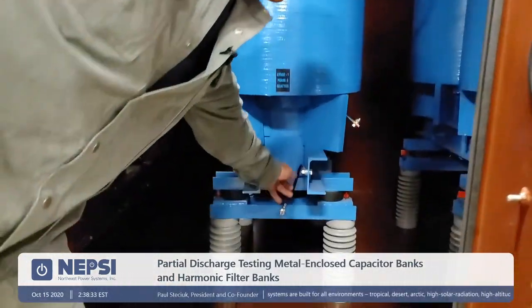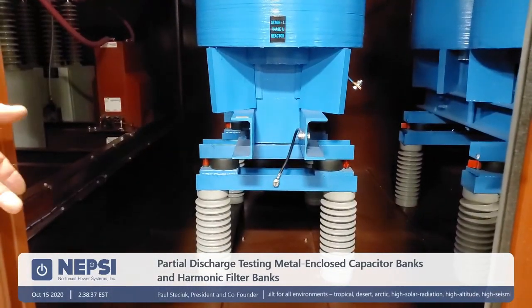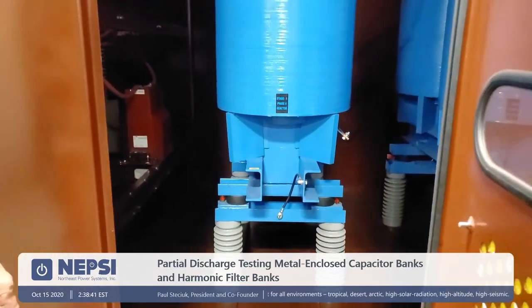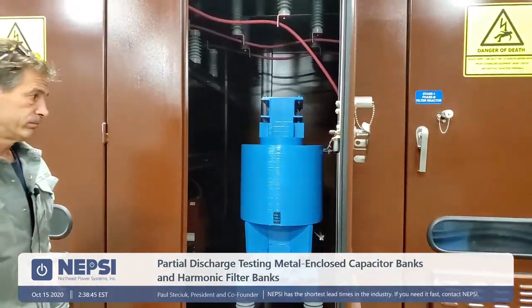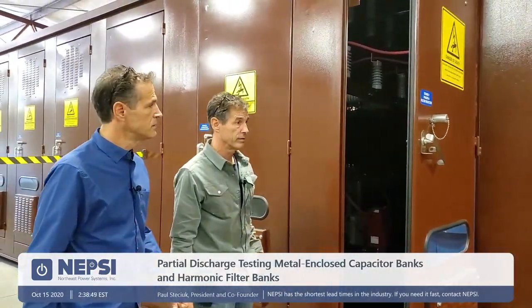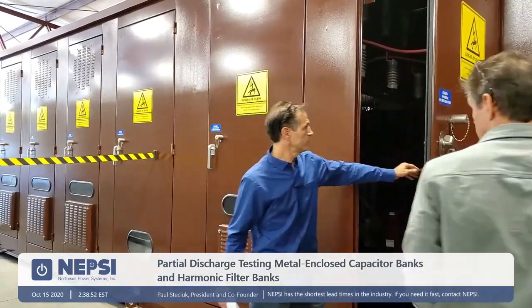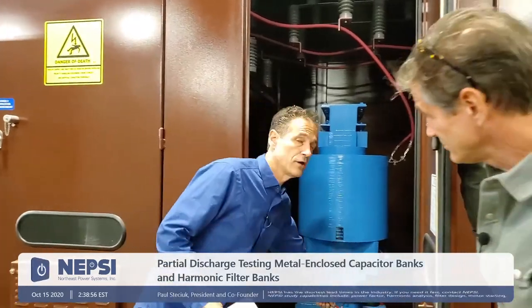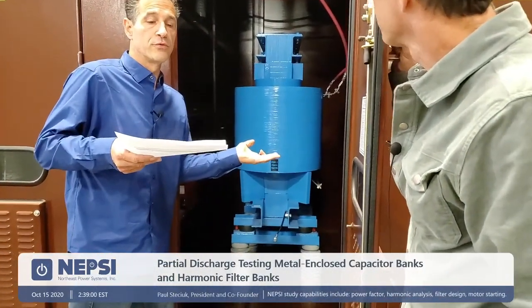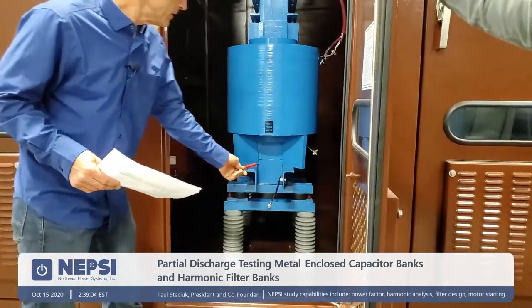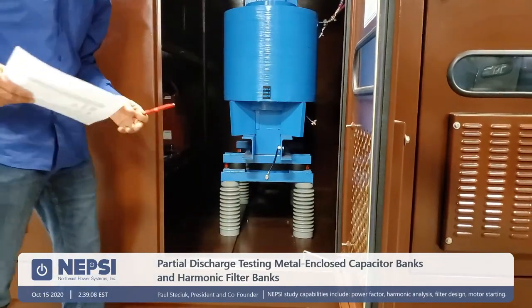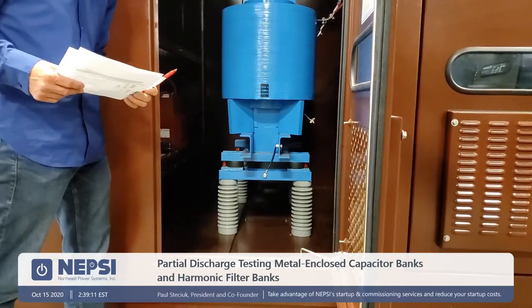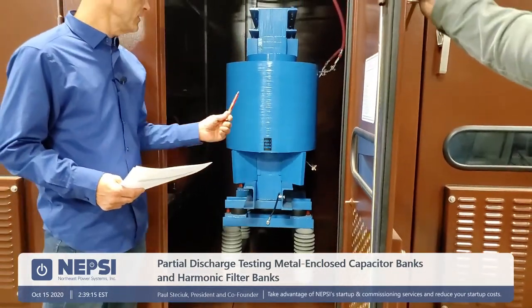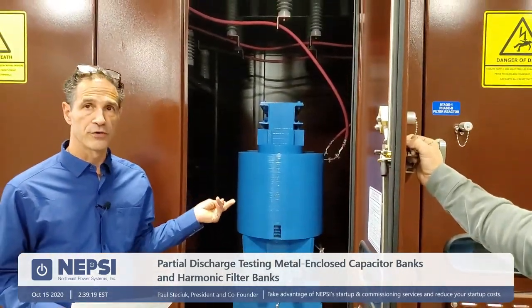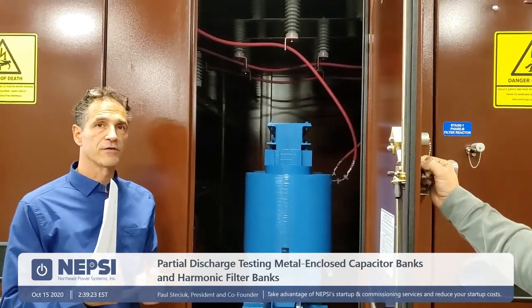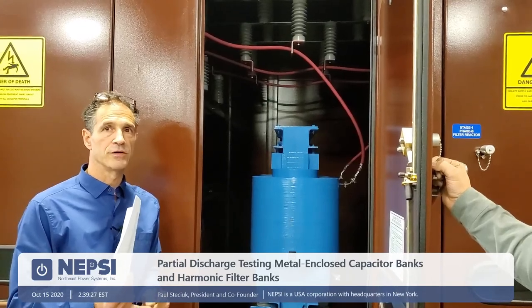For this, the core was not grounded to the lower piece, and the lower piece was just floating in air, and that floating metal caused us to have a greater discharge value that made it fail. So to talk about what this is, it's an iron core reactor. It's floating up on insulators. It rises up in potential. So what we're doing in the test is actually coming up to 40 kV. And this metal part here, if it were left ungrounded, it would be floating, and you would definitely get partial discharge in that region. There would be a significant amount of voltage stress there. So I found that missing strap. We had found that the breaker wasn't grounded properly. The other things that we typically find is if the through wall bushing area is not done correctly, it will fail because of that.